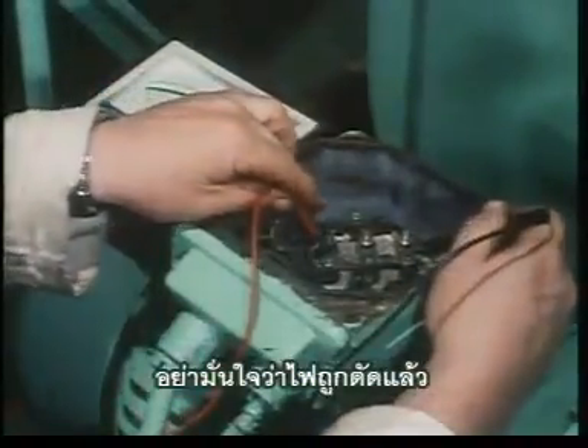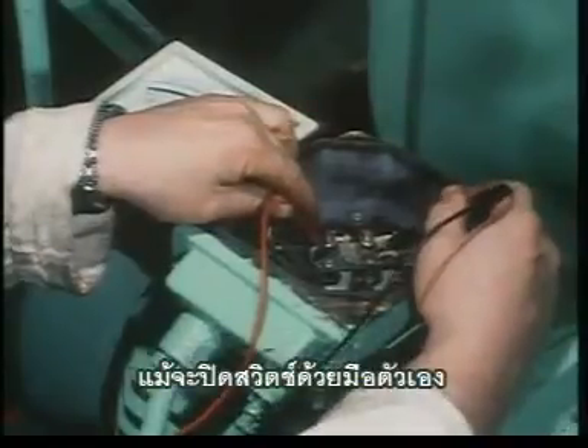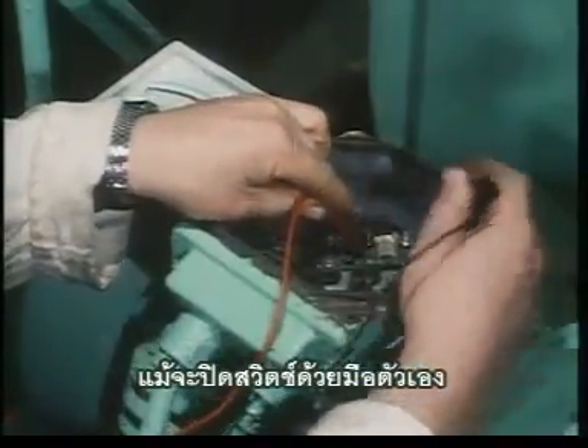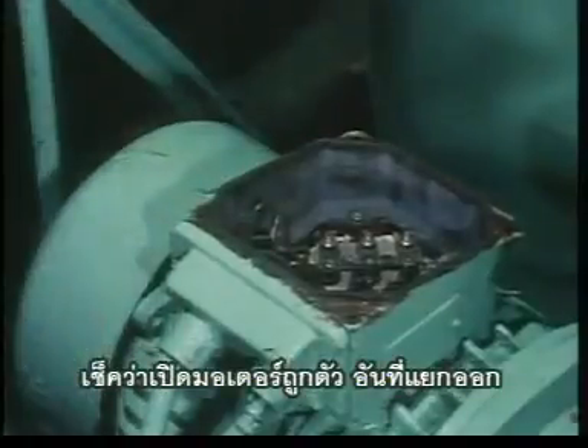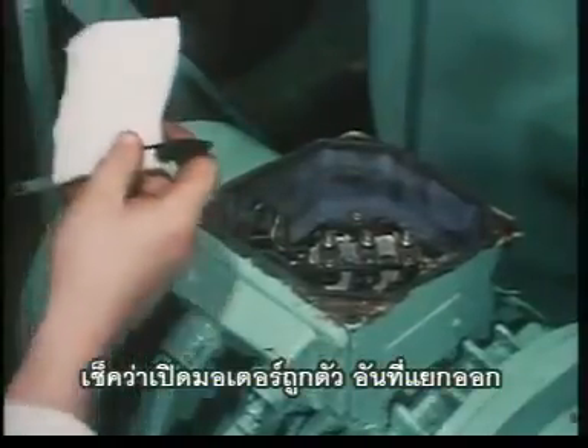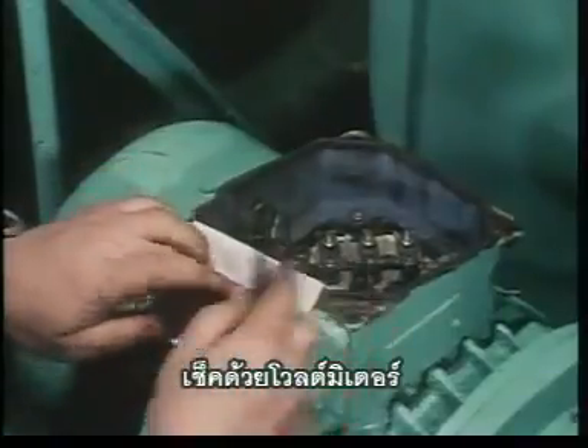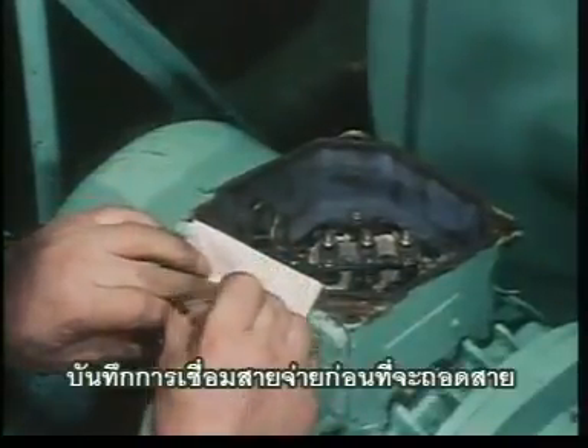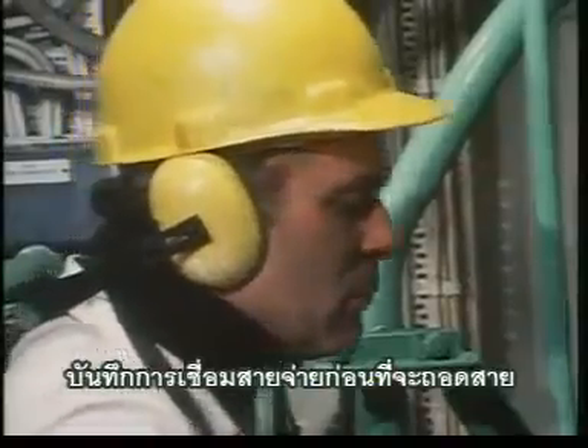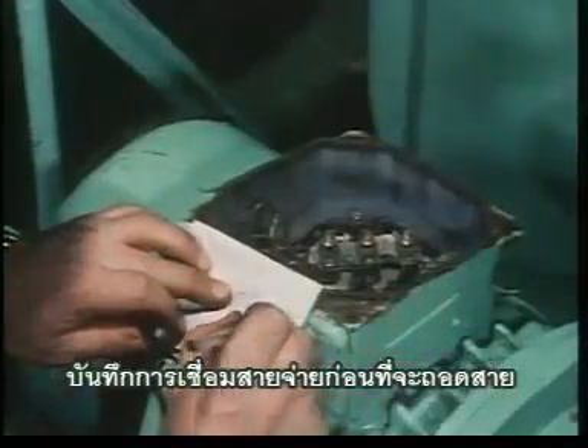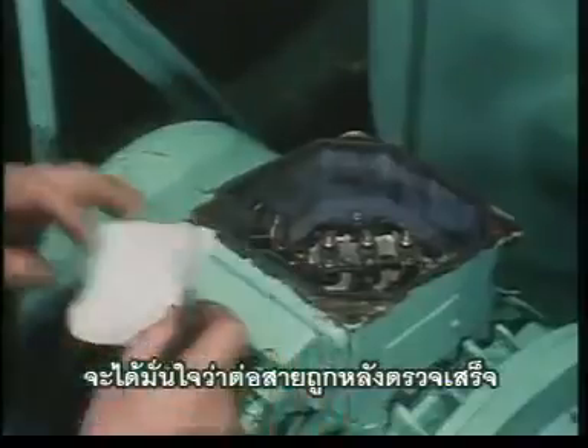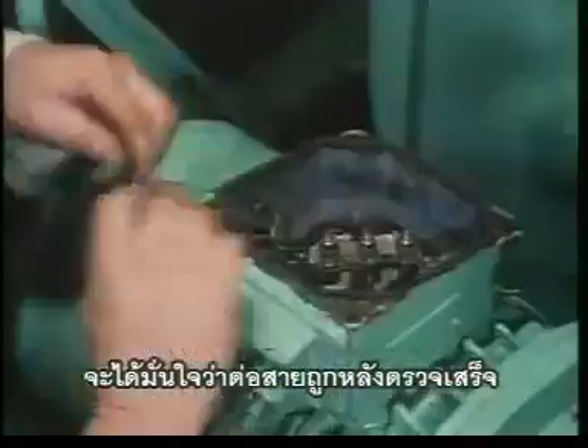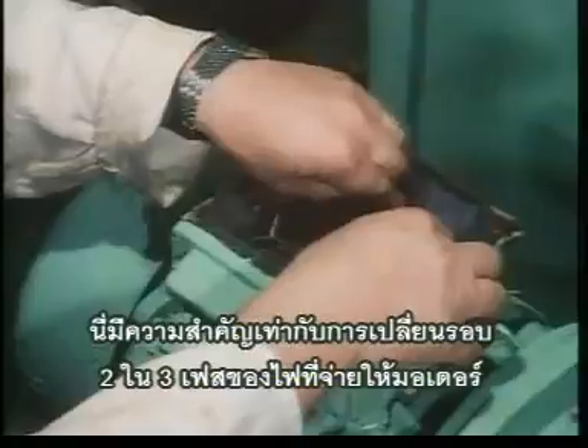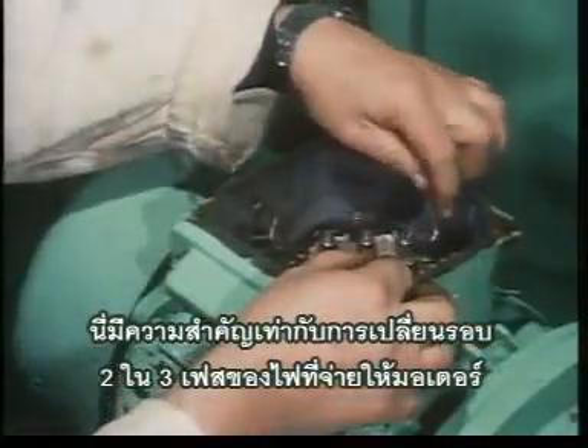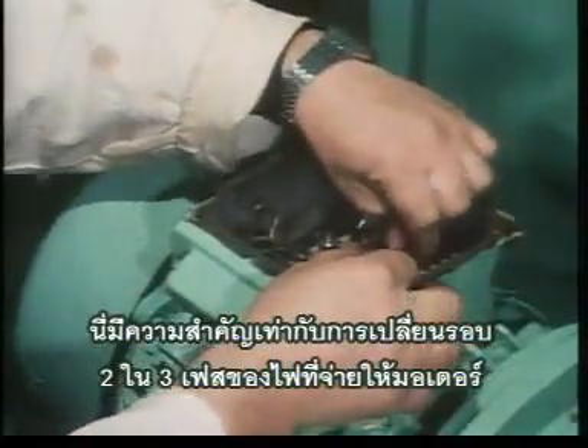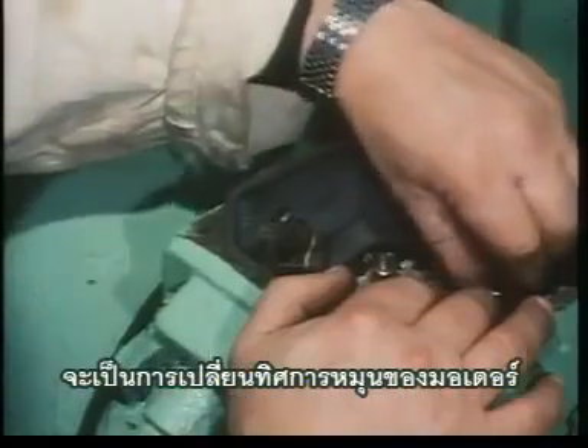The terminals must not be assumed to be dead, even though you yourself switched the supply off. Check that you have opened the right motor, the one which you have isolated. Check it with a voltmeter. A record of the connection of the feeder cables in the terminal box prior to disconnection will ensure correct reconnection after the investigation. This is important, as changing round any two leads of a three-phase supply to a motor changes the direction of rotation of that motor.